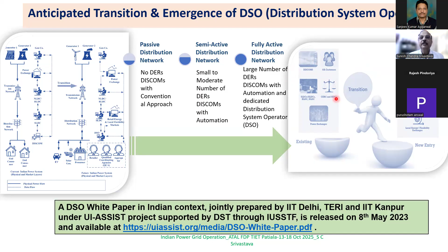Realizing this, and with encouragement from Mr. Suni, as part of one of our Indo-US projects, we worked on the DSO concept, the distribution system operator concept, which has already developed to some extent in Europe and is at a beginning stage in the US as well. A separate distribution system operator will be required, whether it becomes part of the SLDC or part of the area load dispatch center. We have suggested 4 different models and mapped every state to which model they can select. But within 5 to 10 years, every state will have to go for this kind of entity, the distribution system operator.